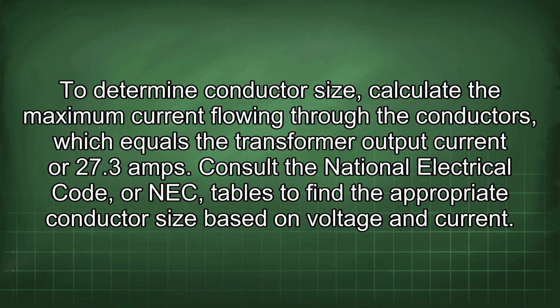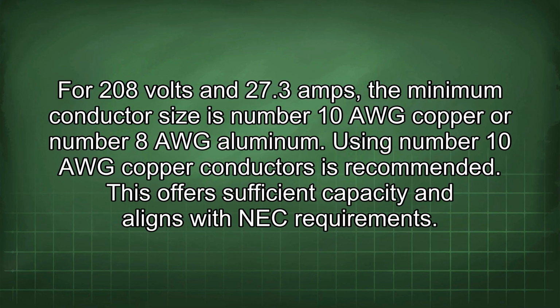To determine conductor size, calculate the maximum current flowing through the conductors, which equals the transformer output current of 27.3 amps. Consult the National Electrical Code, or NEC, tables to find the appropriate conductor size based on voltage and current. For 208 volts and 27.3 amps, the minimum conductor size is number 10 AWG copper or number 8 AWG aluminum.